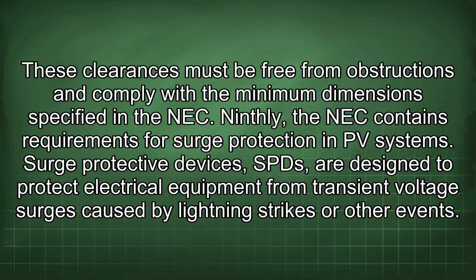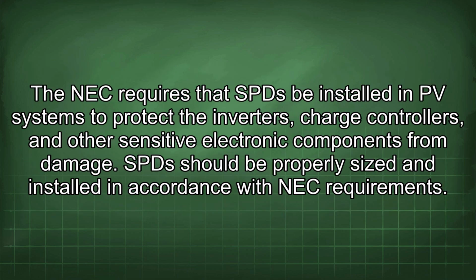Ninthly, the NEC contains requirements for surge protection in PV systems. Surge protective devices, SPDs, are designed to protect electrical equipment from transient voltage surges caused by lightning strikes or other events. The NEC requires that SPDs be installed in PV systems to protect the inverters, charge controllers, and other sensitive electronic components from damage. SPDs should be properly sized and installed in accordance with NEC requirements.